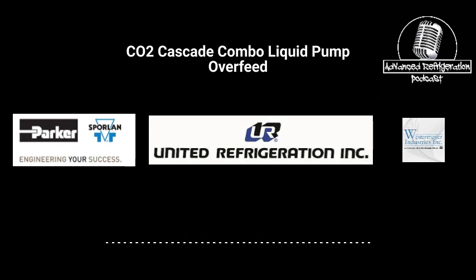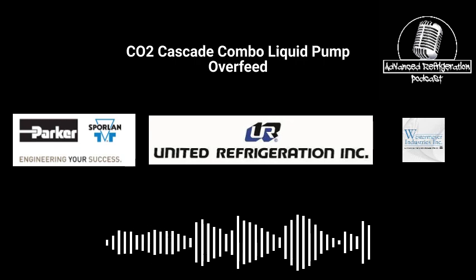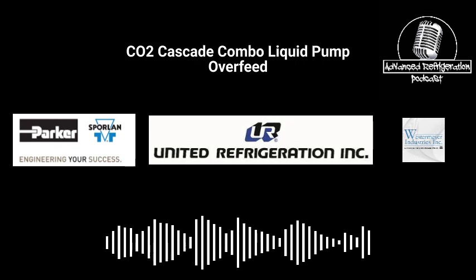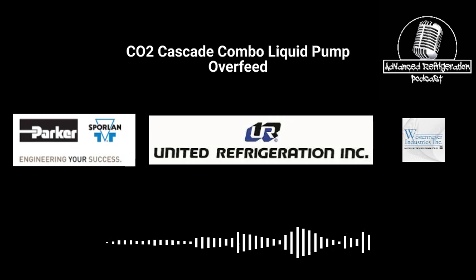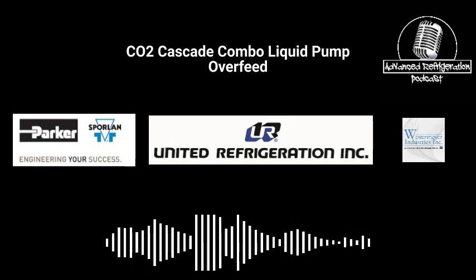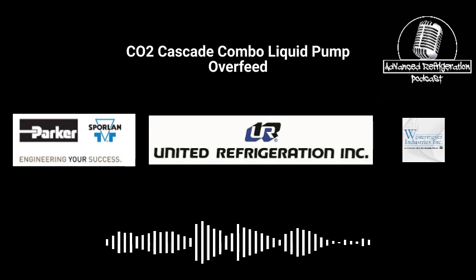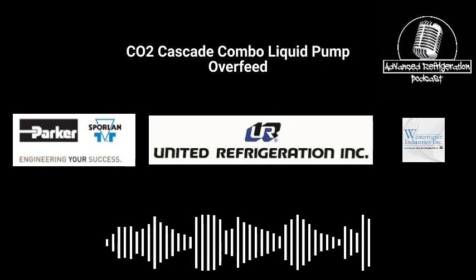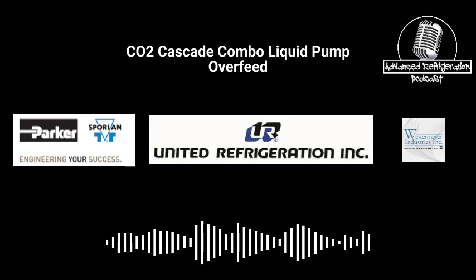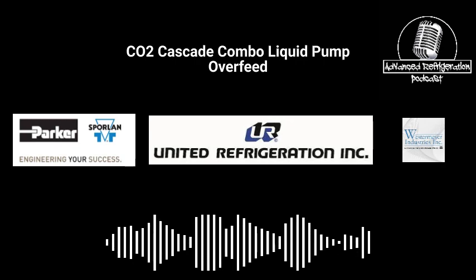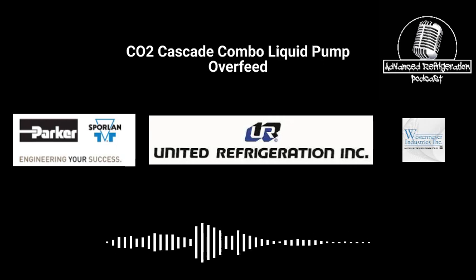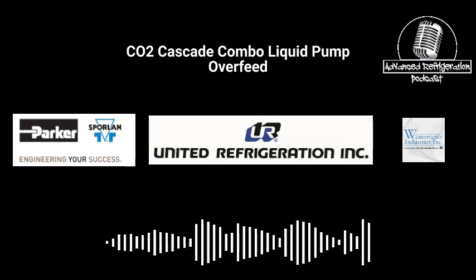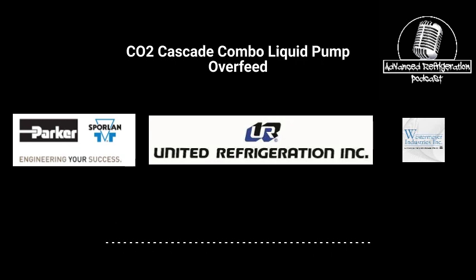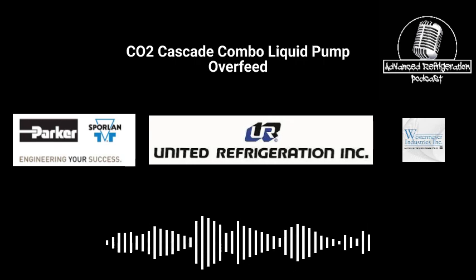And the systems I've seen, I haven't seen the Hill one, but I've seen Carnot's version, and a couple other different versions of it. Basically, it's no different than the Target Cascades, where they have an HFC or HFO cooling it down. They're still doing that, and they're just using the receiver like you would normally have on the Cascade rack for the CO2 side, and the liquid pumps coming off of that. So they're not actually doing liquid pumped. They're not doing the thermal siphon. They're using the discharge gas from the compressors going right to the heat exchangers. So you have that constant forced volume there. You don't have that lockup, from what I've seen, from the systems I've worked on.